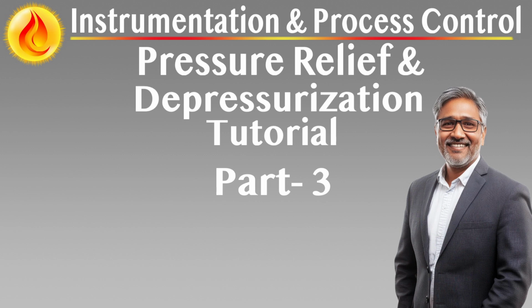Sectioning of process systems for depressurization. To manage emergency depressurization effectively, especially in large, complex facilities, process systems should be divided into discrete fire zones or depressurization segments. This strategy helps to control the peak flow rate into the flare or vent system and limits the impact of depressurization on the facility's utility systems and flare capacity.